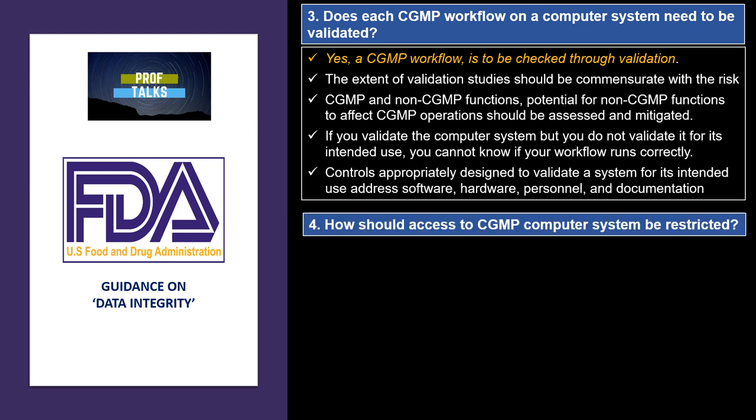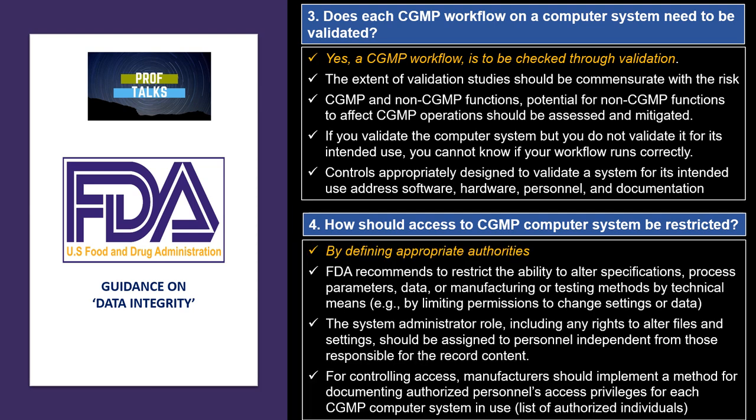The next question is: how should access to CGMP computer systems be restricted? The answer is by defining appropriate authorities. It is the firm's responsibility to maintain a list of authorized persons with roles defined appropriately. FDA recommends restricting the ability of alteration by limiting permissions to change settings or data. The system administrator role should never be given to a person who is responsible for recording the data in the same department — it should be an independent person.